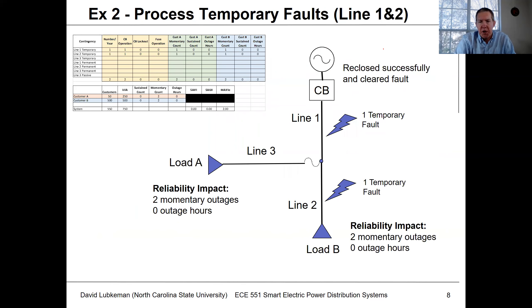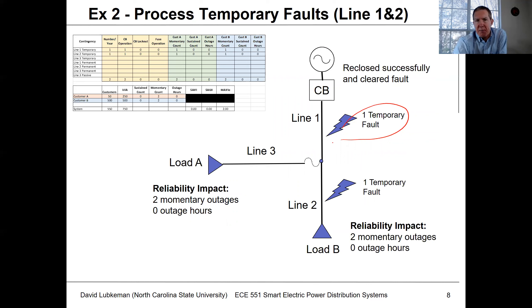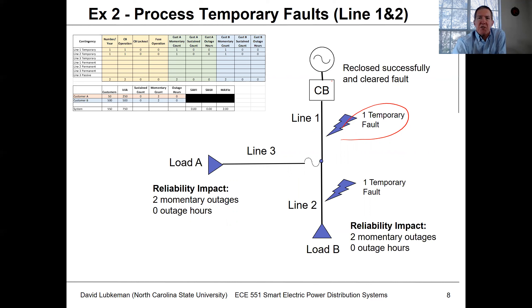Let's look at how we populate the table, focusing on lines one and two for temporary faults. A temporary fault is one that can be cleared by a reclosing operation at the station breaker — we don't even need fuse savings set for anything on the main feeder, since anything there can be cleared by the station circuit breaker. We normally have reclosing activated for the station breaker.